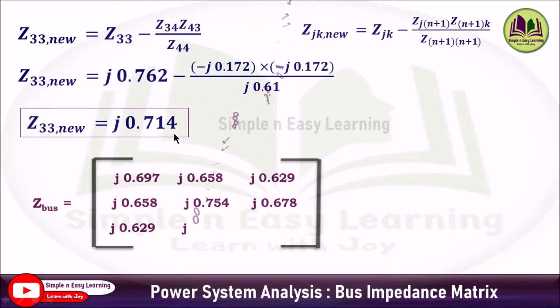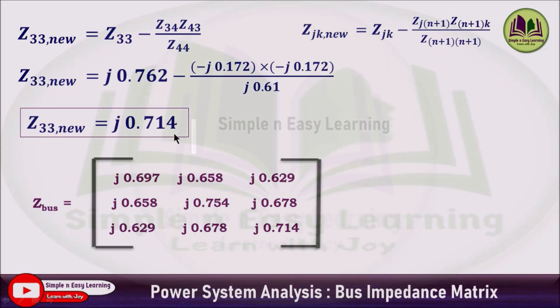Substituting into matrix format, these nine parameters form the final Z-bus matrix, considering all reactances in the given diagram. This is how you solve this problem to calculate the bus impedance matrix using the bus building algorithm method.